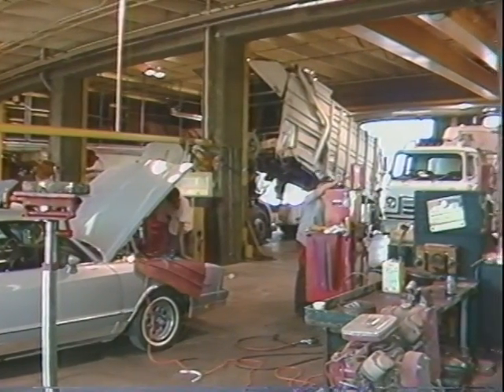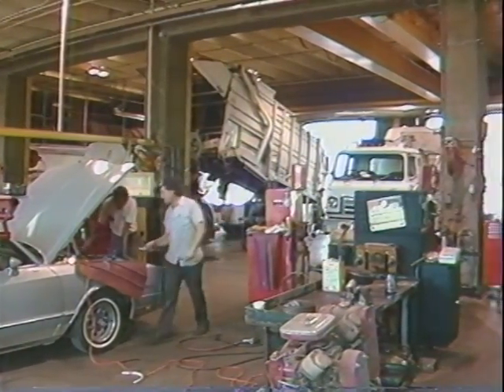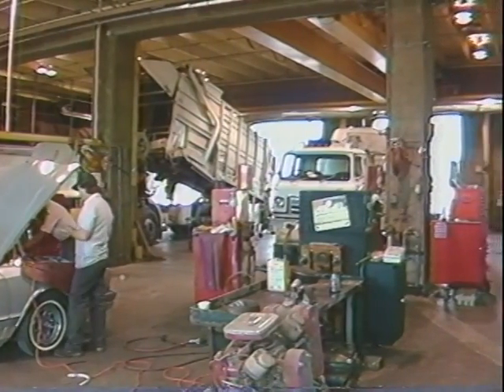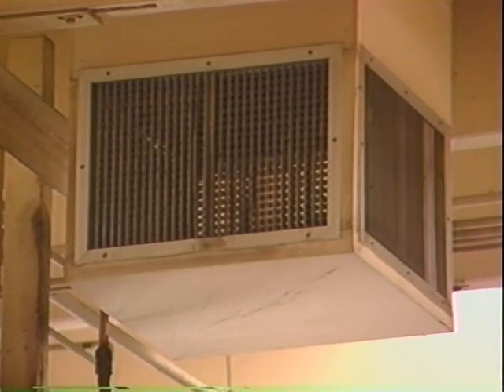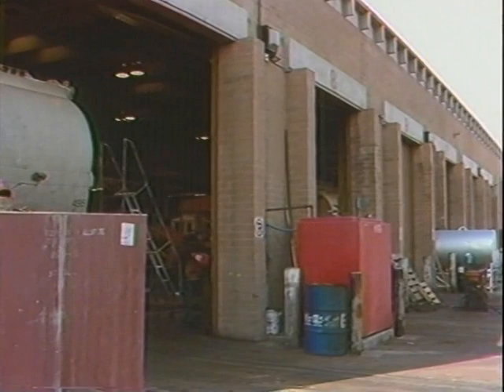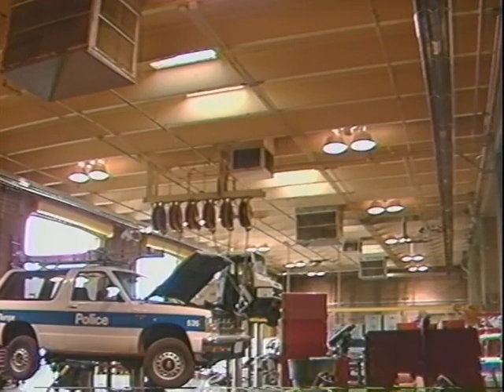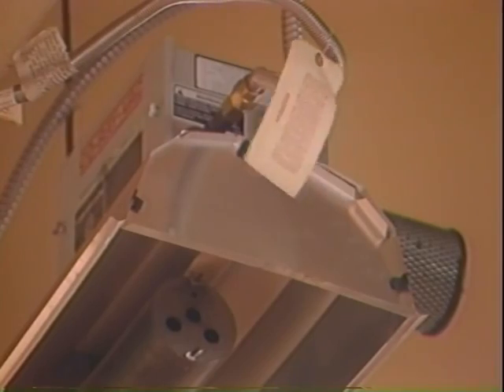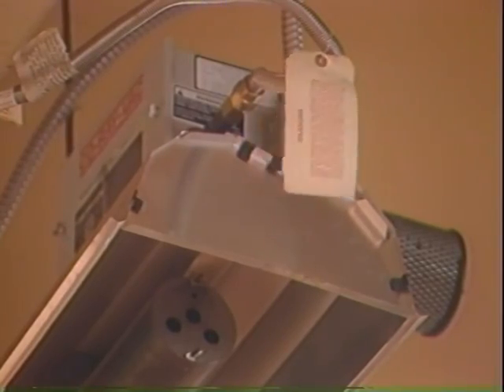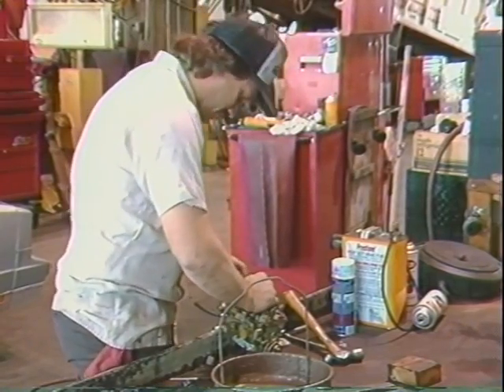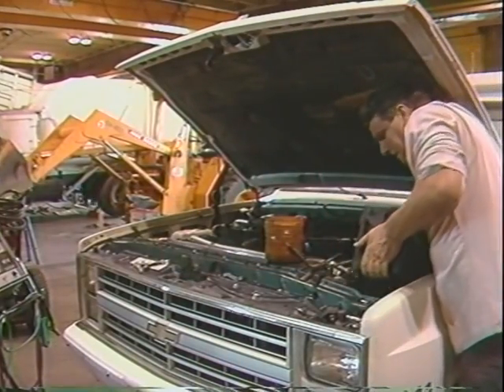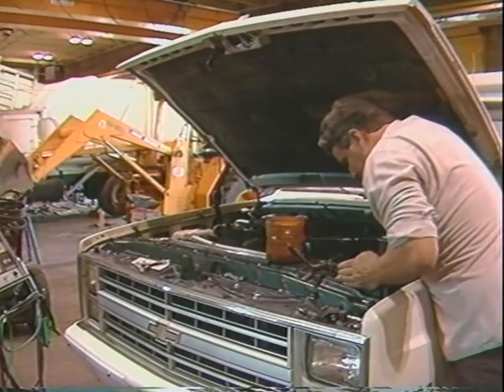Although cooling is the major concern in the desert, efficient heating was the problem here at the city's vehicle maintenance facility. The old electric heaters could not overcome the effect of 12 bay doors constantly left open. Heated air was siphoned directly to the outside, with little or no effect in the work area. The solution was to install gas-fired radiant heaters. With a radiant heat system, objects are heated rather than air. Mechanics now work in comfort with warm tools and equipment, even when the doors are open.